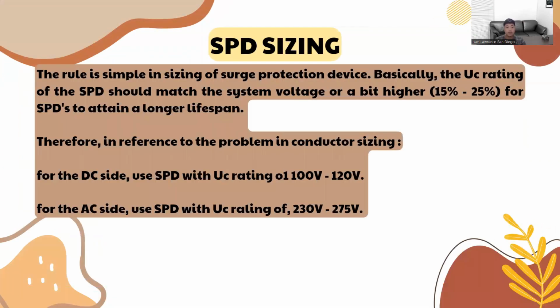SPD sizing. The rule is simple in sizing of surge protection device. Basically, the UC rating of the SPD should match the system voltage or a bit higher, 15% to 25% for SPDs to attain a longer lifespan. Therefore, in reference to the problem in conductor sizing, for the DC side, use SPD with UC rating of 1,100 volts to 1,120 volts. For the AC side, use SPD with UC rating of 230 volts to 275 volts.